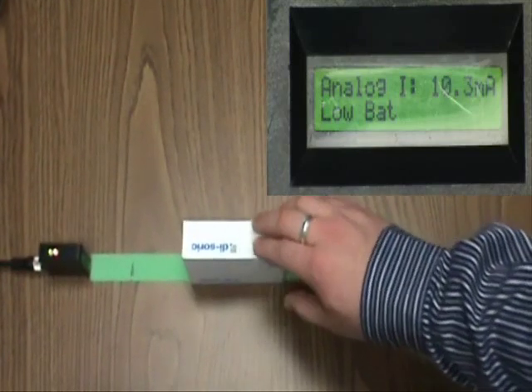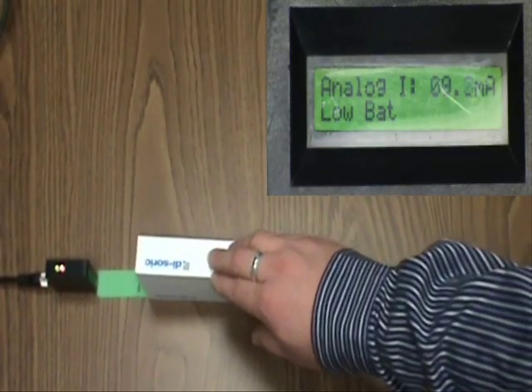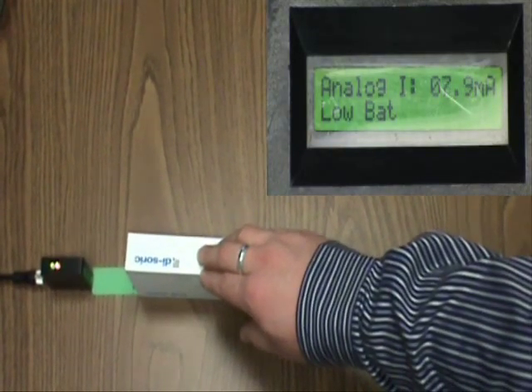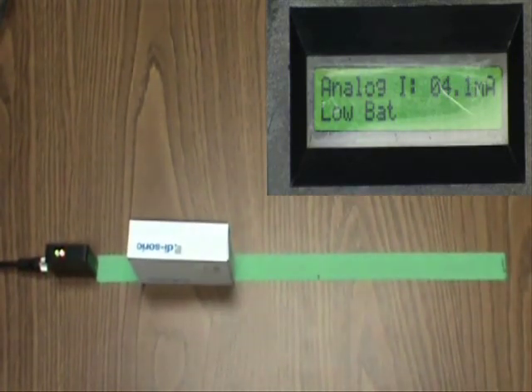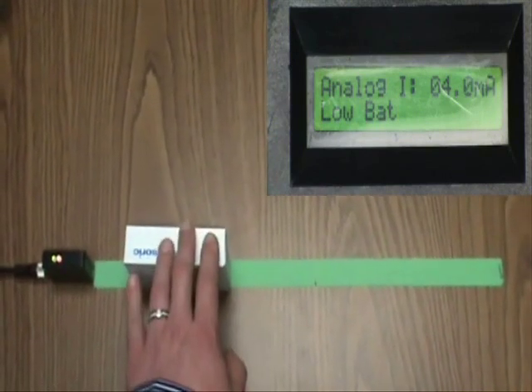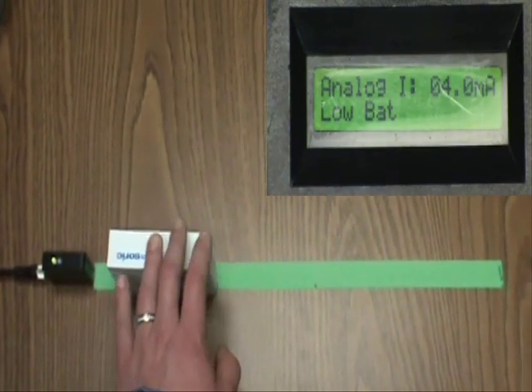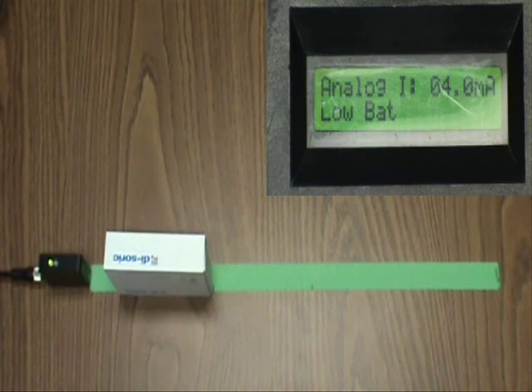As we approach the minimum distance of 50mm, our output now sits at the 4mA output mark. Moving past this will trigger an out-of-range value.